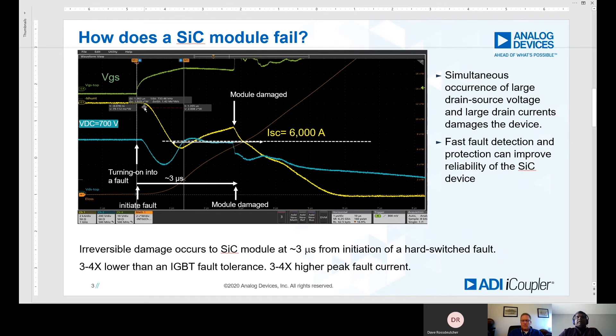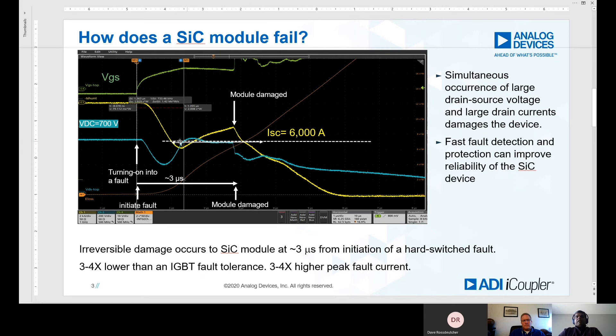That's like the max we've seen. If you look at the waveform on the top, the green waveform is the gate voltage going up, and the yellow trace is the short-circuit current — reversed, so you should read it as going up. The teal trace is the drain-to-source voltage across the silicon carbide. This is a case where we're turning on into a fault: as the gate voltage goes above the threshold, the current starts increasing. This is a 400-ampere rated module and the peak current reaches up to 6,000 amps. Simultaneously, the drain voltage is sitting at around 300 to 400 volts, so this is deep in saturation for the SiC device. When you have simultaneously such high voltage and current, there's just so much heat dissipation on the part, and after about 3 microseconds from the beginning of turn-on, the module is damaged — it usually takes both the gate driver and the SiC module. You can hear a pop on the bench.